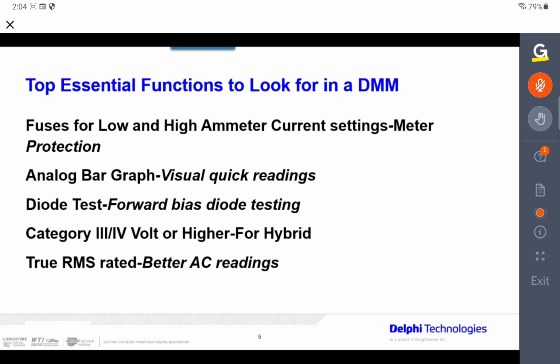You also have to have an analog bar graph if at all possible - not all meters have that. The analog bar graph is that little bar graph you'll see at the bottom. That updates 40 times a second on a Fluke, I know for a fact, while the screen updates on the meter readings only 4 times a second.